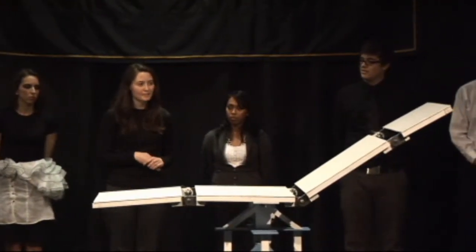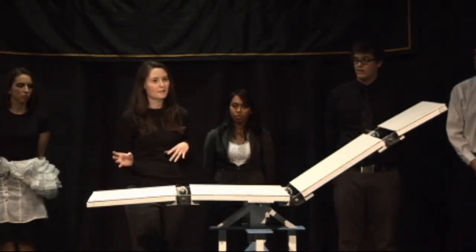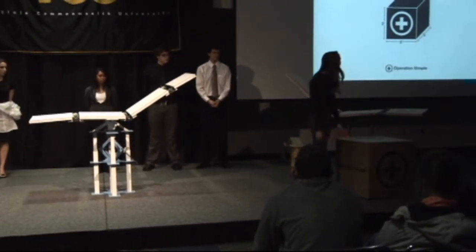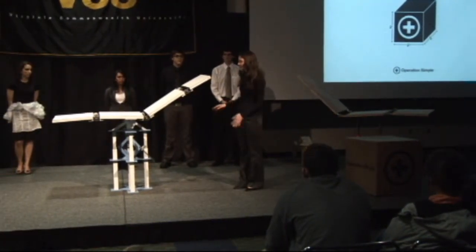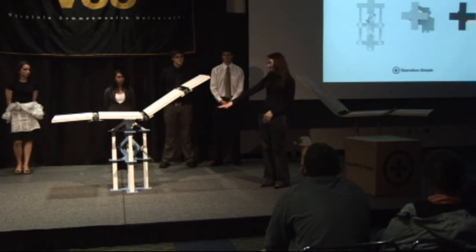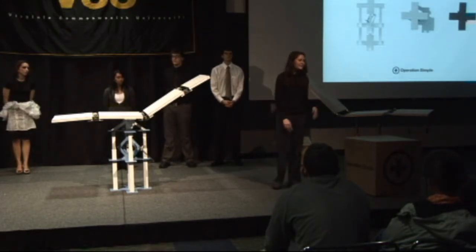And though this operation table accommodates for 90% of the population and spans 6 feet, we really needed to compact it to the smallest container possible. So this is how we arrived at the 2 foot by 2 foot by 2 foot cube here, cardboard cube. And when we first started prototyping this design, the form really lent itself to the cubic shape. The gimbal, the mechanical box assembly fit nicely within, as you saw earlier, within the folded segments. And that's really how we arrived at the cube.